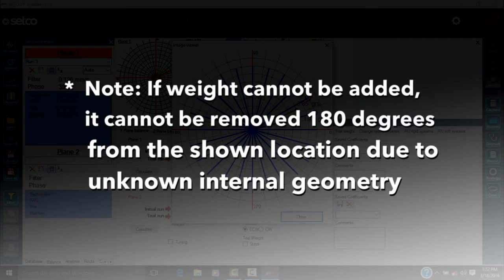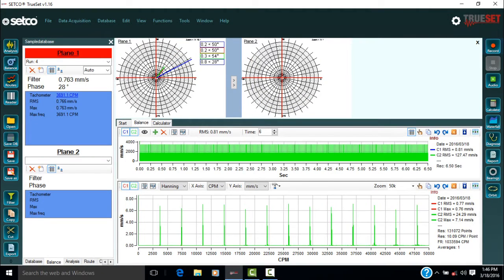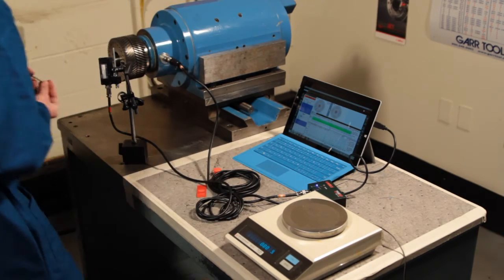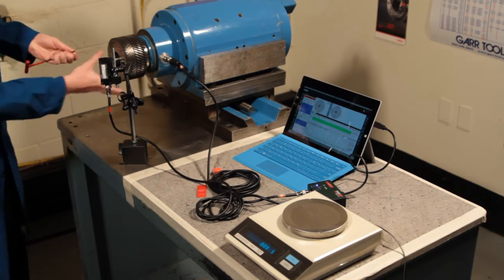Click on the graph to see where to add balancing weight. If weight cannot be added, it cannot be removed 180 degrees from the shown location. Remember to remove the trial weight if desired. The weight must be added or removed in the same rotational radius as the trial weight.